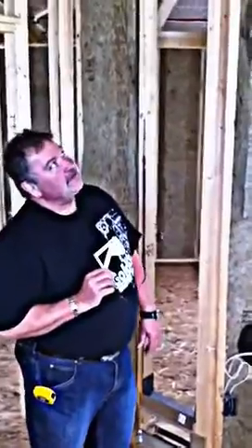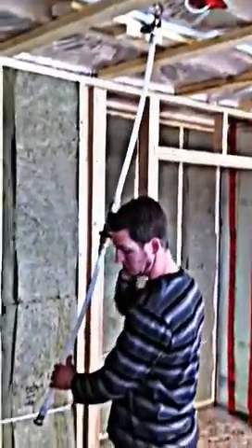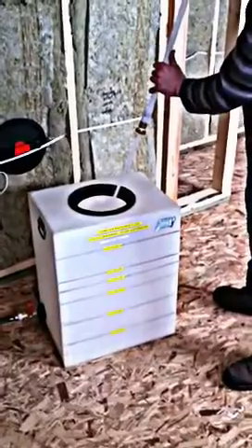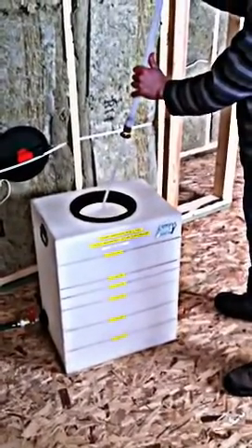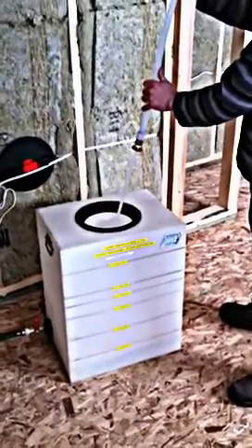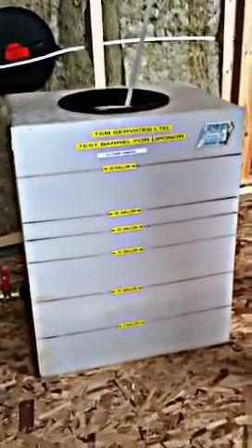So Terry, what are we doing here today? We have 18 gallons of flow from our sprinkler system. Clark's holding a test line and we're going to start putting it in the water. What we're trying to see here is how fast we can fill this tank up, and there's a specified amount of water that we need to meet the NFPA requirements within a minute.